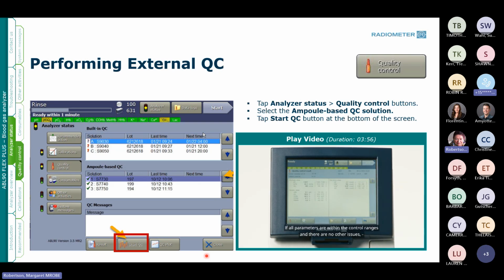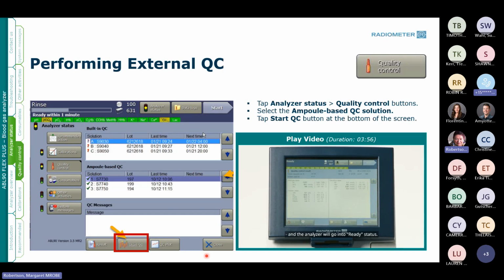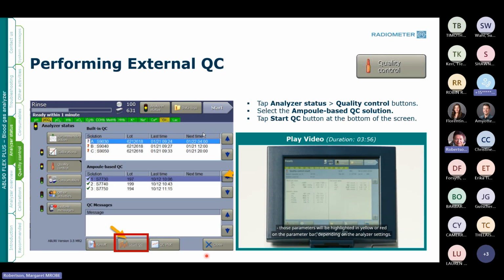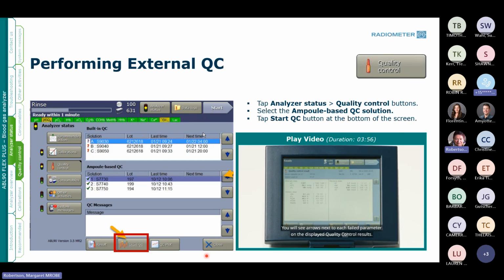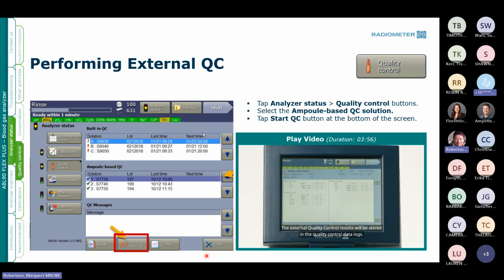If all parameters are within the control ranges and there are no other issues, the parameter bar will show all parameters in green, and the analyzer will go into ready status. If one or more of the parameters violates the control ranges, those parameters will be highlighted in yellow or red on the parameter bar, depending on the analyzer settings. You will see arrows next to each failed parameter on the displayed quality control results. The external quality control results will be stored in the quality control data logs.